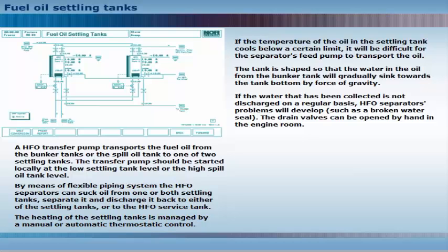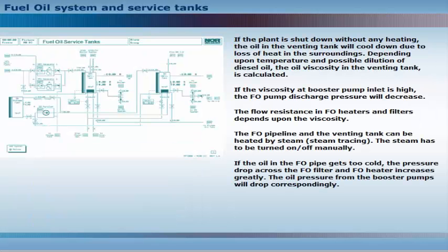The drain valves can be opened by hand in the engine room. If the plant is shut down without any heating, the oil in the venting tank will cool down due to loss of heat in the surroundings. Depending upon temperature and possible dilution of diesel oil, the oil viscosity in the venting tank is calculated. If the viscosity at booster pump inlet is high, the fuel oil pump discharge pressure will decrease. The flow resistance in fuel oil heaters and filters depends upon the viscosity. The fuel oil pipeline and the venting tank can be heated by steam — steam tracing.